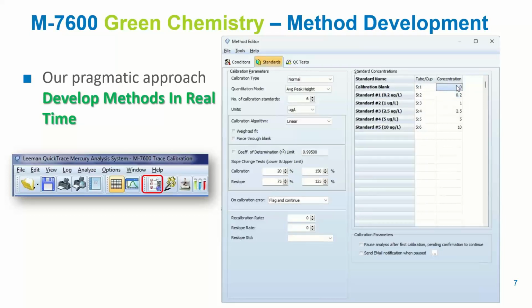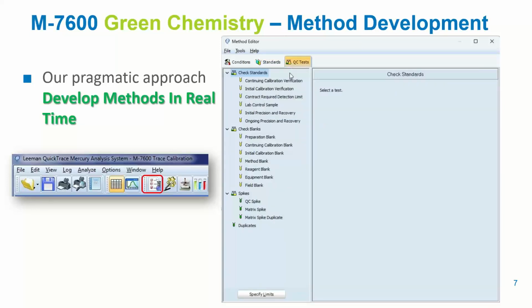And in the concentrations, you just type those in the last column. There's also an option to pause analysis after first calibration pending confirmation. I always like that option because you won't waste any samples if the calibration didn't go as expected for some reason. And in the final tab, we have QC test.